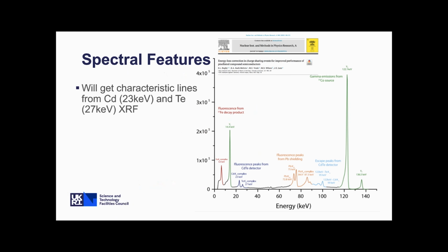It's also worth noting some of the spectral features in the spectrum. When you have an exposure, you're going to get quite a few different lines, which might take some explaining. Again, from a paper from Leicester, in this case for a cobalt 57 source, you've got a 122 peak, but then you also have the characteristic lines from cadmium and tellurium. So you're measuring the 23 and 27 keV peaks from the detector itself.